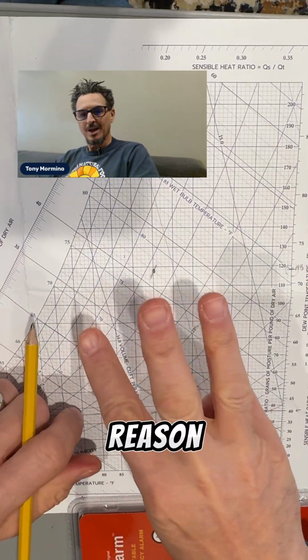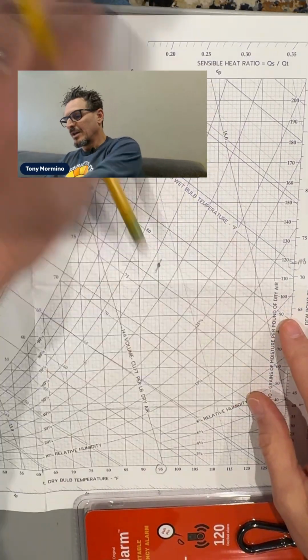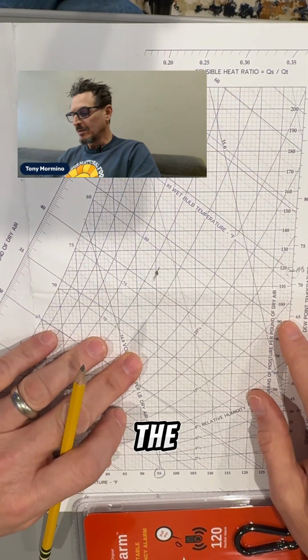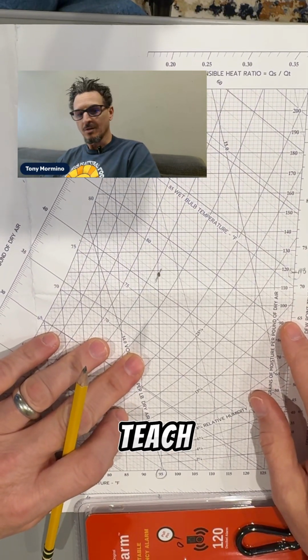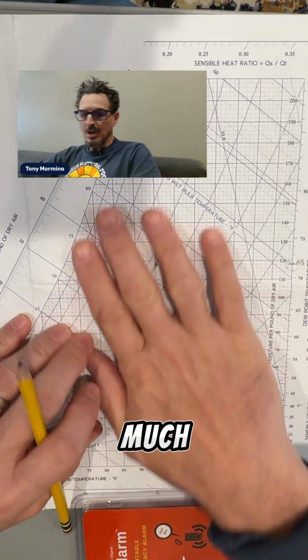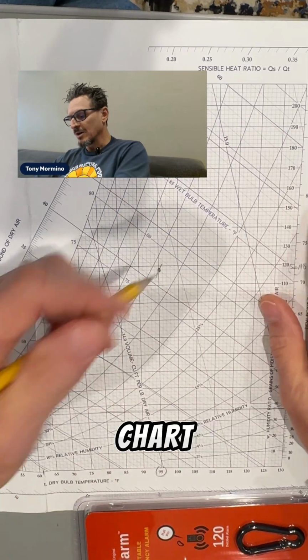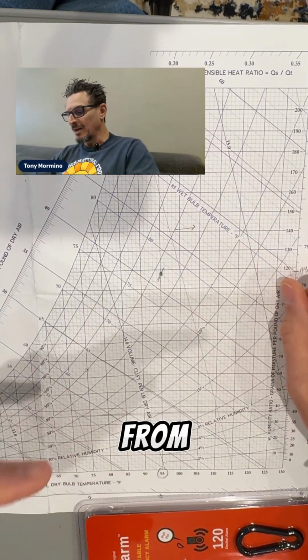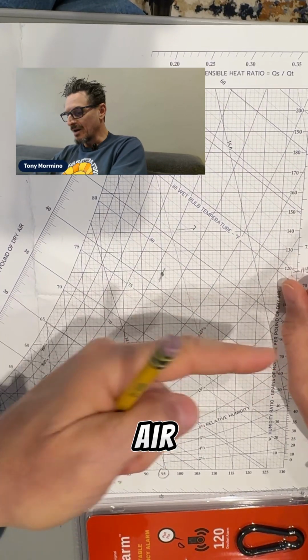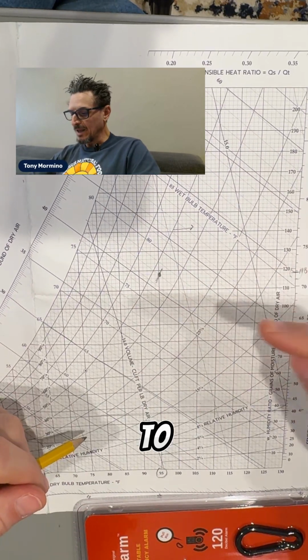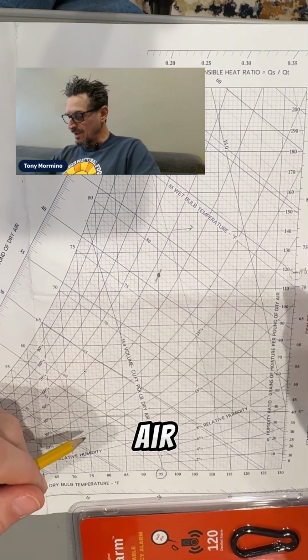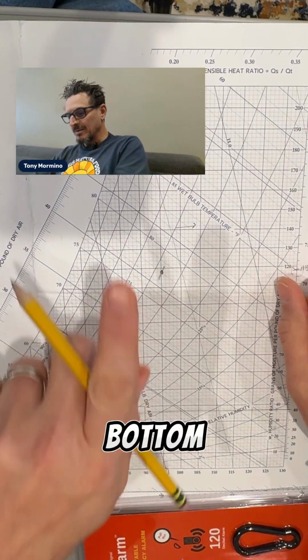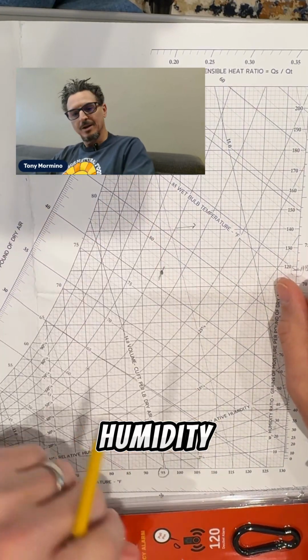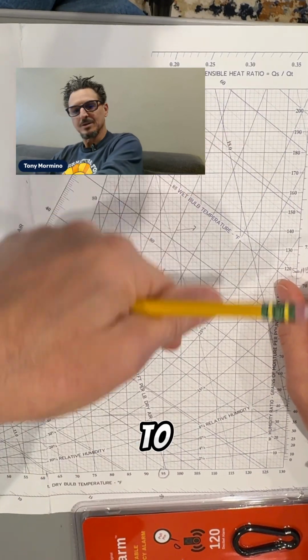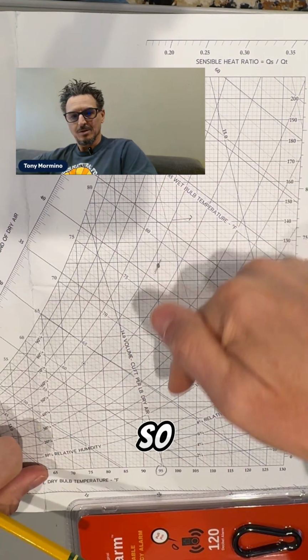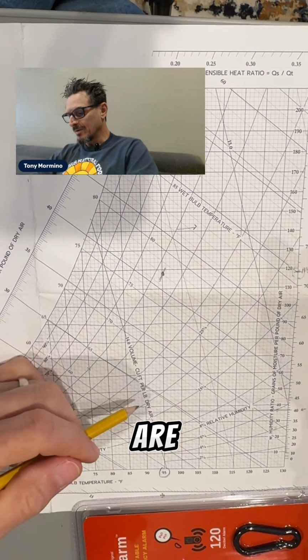The third reason I like to use the psychrometric chart is for me to understand the processes of air and to teach the processes of air, which is much easier to show on a psychrometric chart. So if you're going from left to right, you're heating the air. If you're going from right to left, you're cooling the air. If you're going from the bottom to the top, you're adding humidity. And if you're going from the top to the bottom, this way, you are removing humidity.